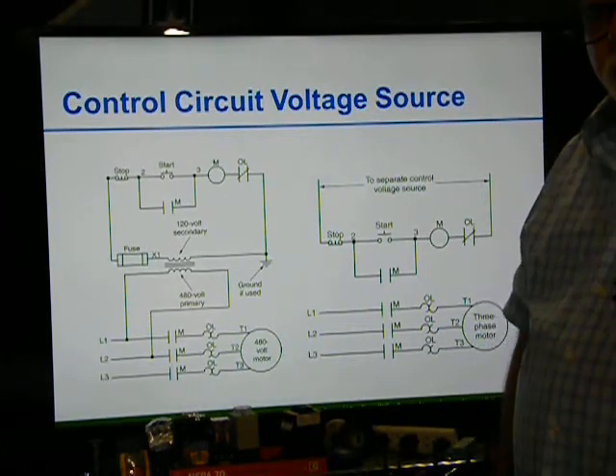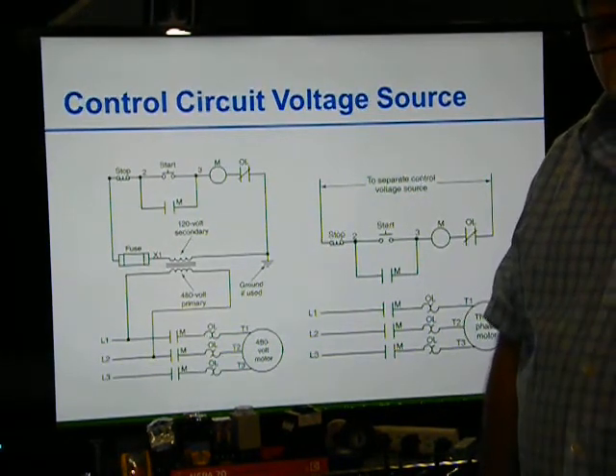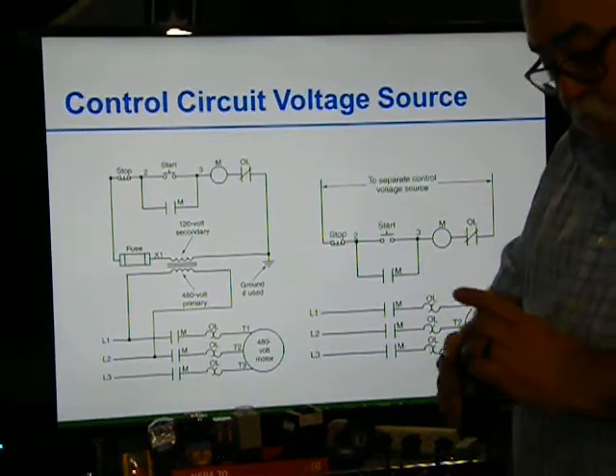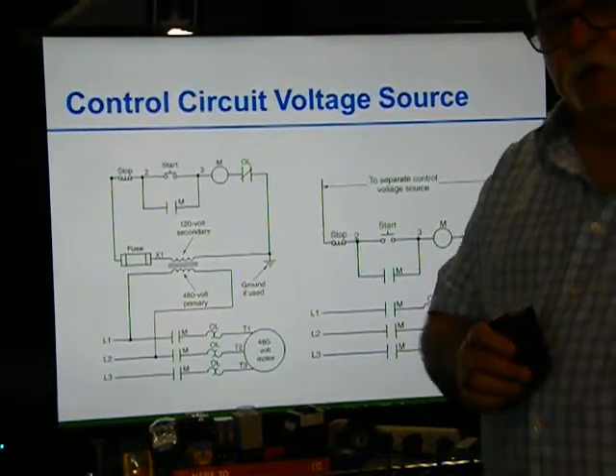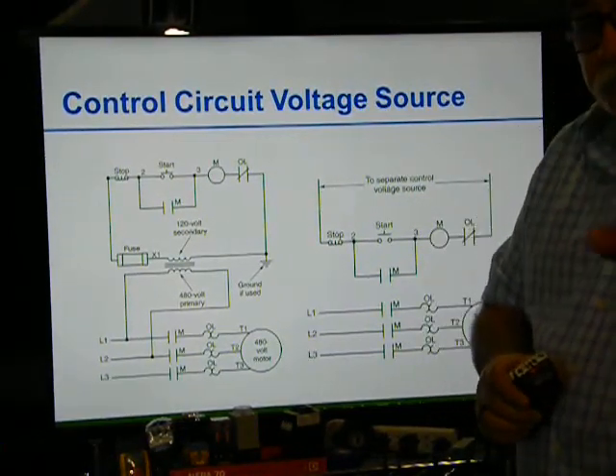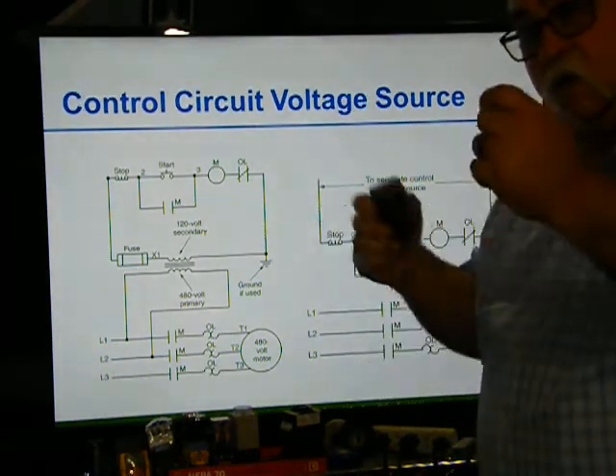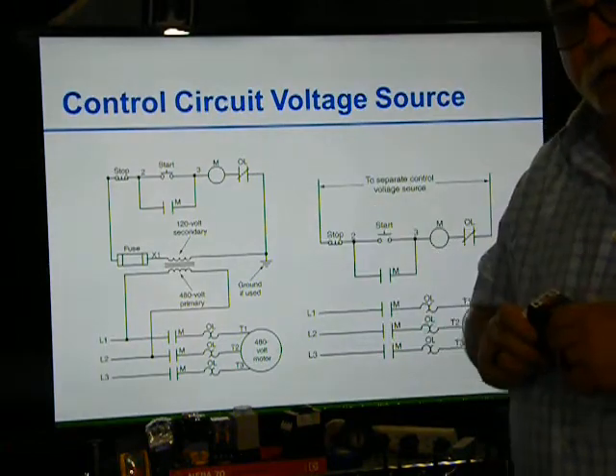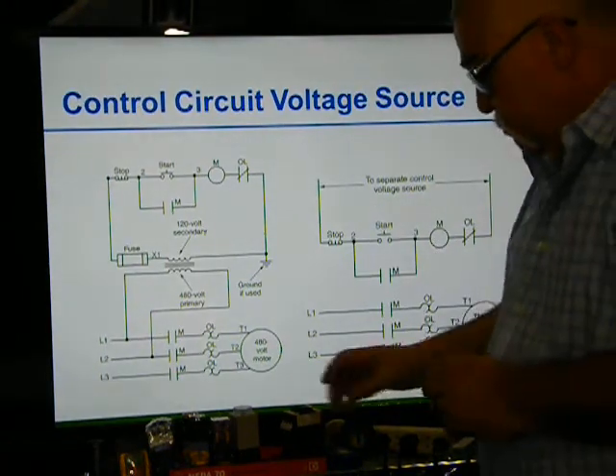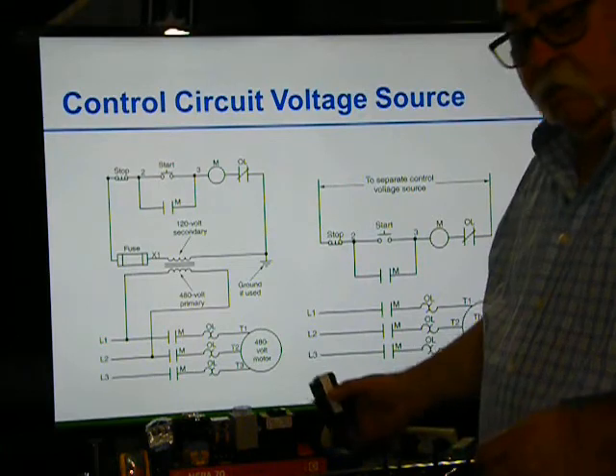Before you hit the reset button, make sure you check that your motor's good. If somebody else says, oh no, everything's fine, it just needs overloads, no. Get your tester out: hot to ground, hot to ground, hot to ground, hot to hot, hot to hot. Make sure the motor is not bad, or you can have this thing blow off the wall in front of you.